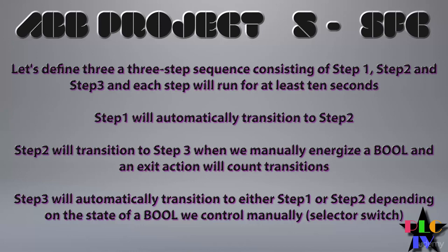Once we do get to step three, we want to be there for ten seconds as well. After that ten seconds, we want to automatically transition back to either step one or step two. What's going to make the difference is the state of another bool. Think of that like a toggle or a selector switch — if it's in one state we go to step one, if it's in the other state we go to step two. It doesn't really matter which state is assigned to which; you're in full control of that.